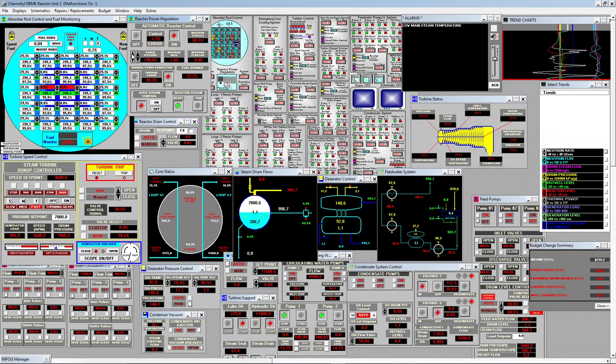I forgot, but you can do this right away after the last fuel bundle. And you see the center core only is engaged. I don't know why. It should not be during normal operation. During normal operation, it should be disengaged. Central core only is used during startup to get the most homogeneous possible activity distribution longitudinally in your reactor core. But later, to have a higher controllability of the reaction, you need to have it disengaged so you act on all the control rods, not only on the center core control rods.